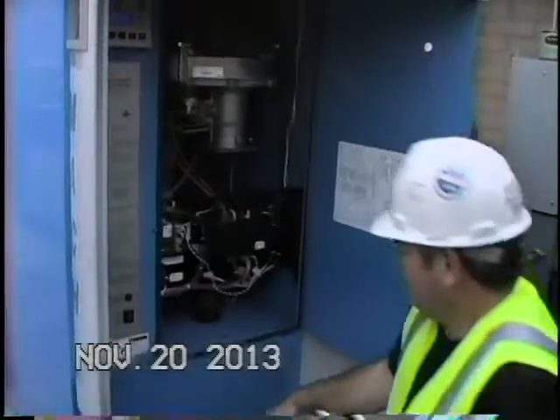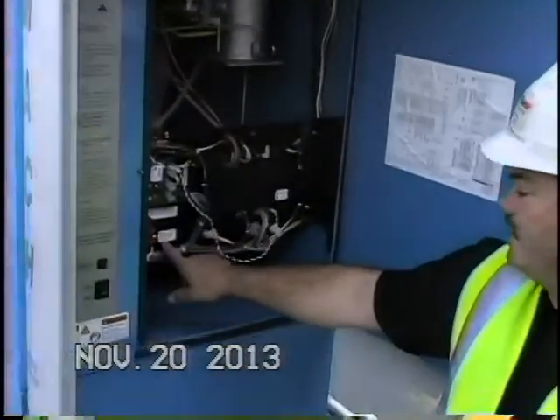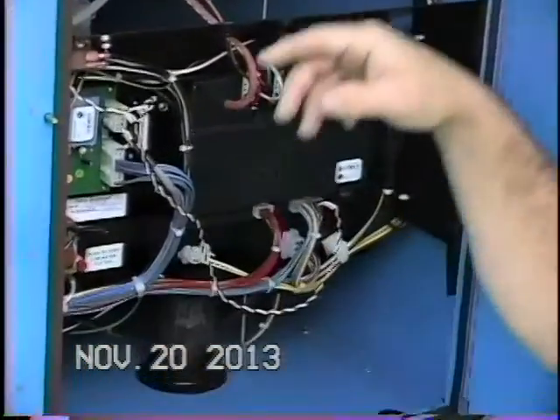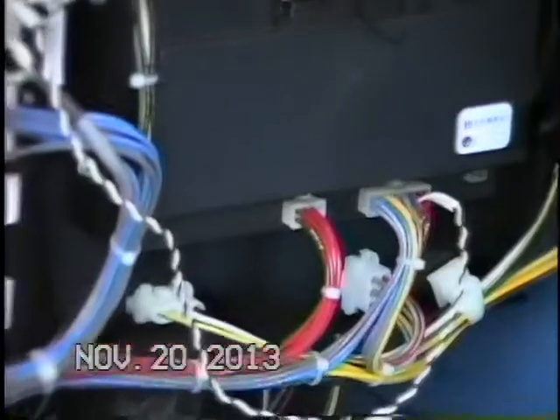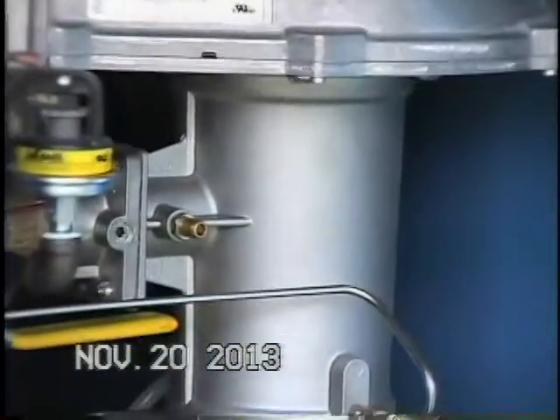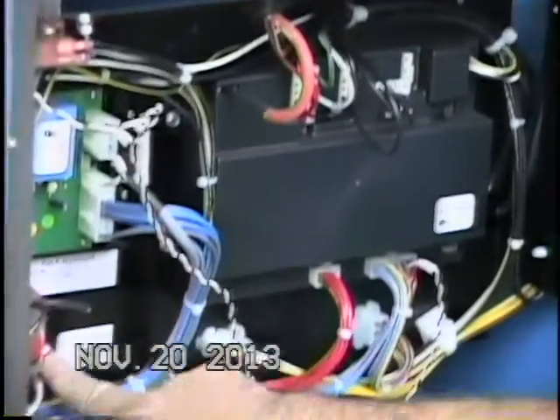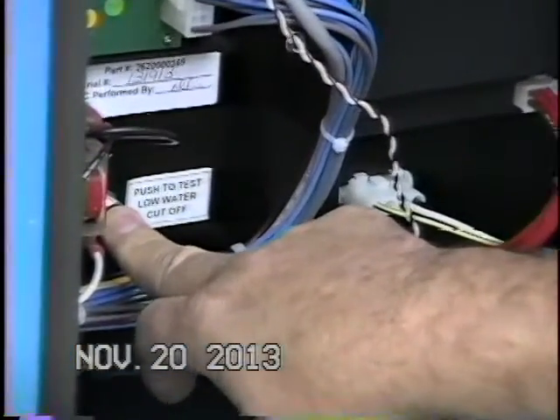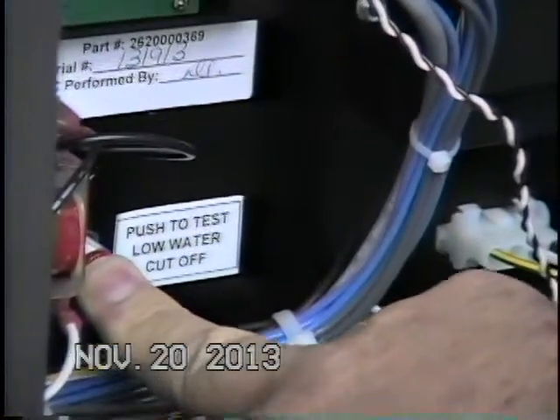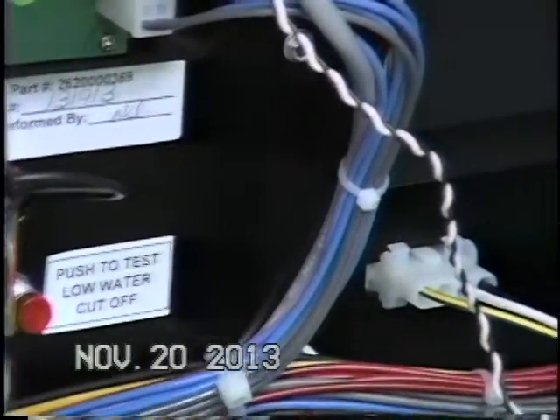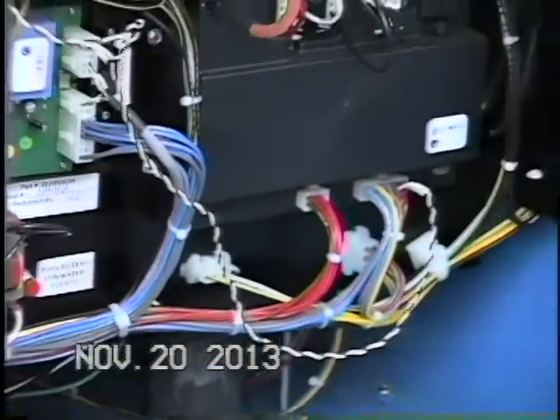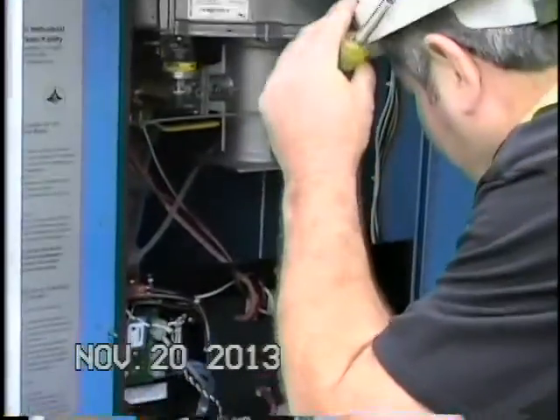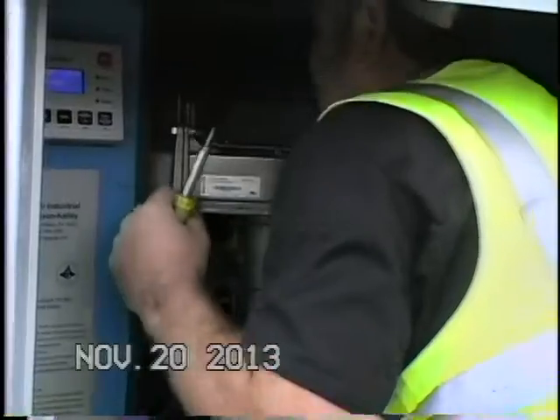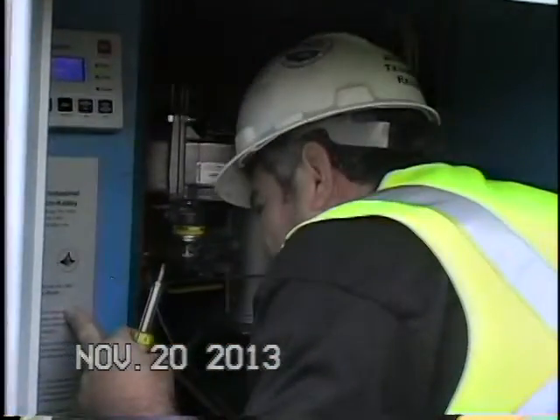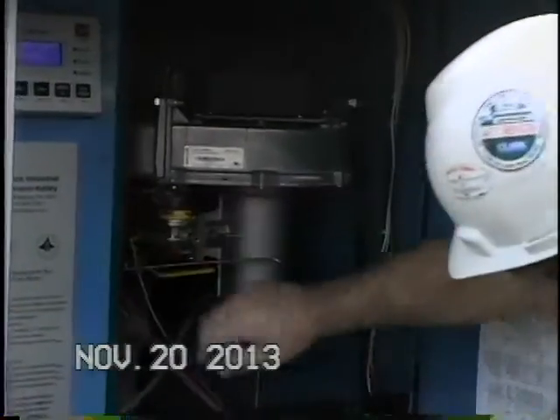So, here's one of the tests, the low water cutout. So if we push this, we see the fire just went out. So it's satisfied on its heat, but if we push this, okay, so now it would have shut down our boiler. Okay? Let's see where the gas is at. Okay, here's our gas valve.